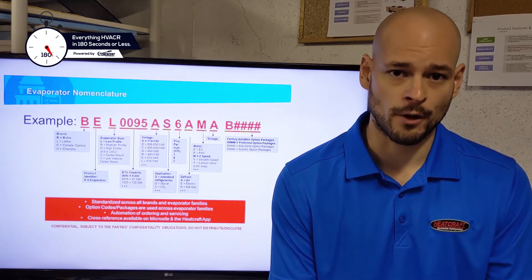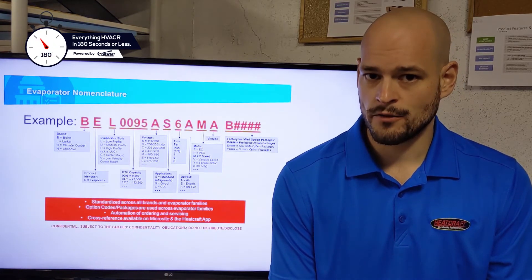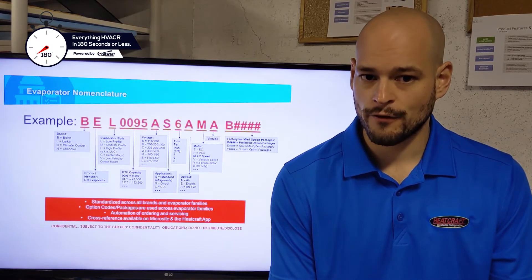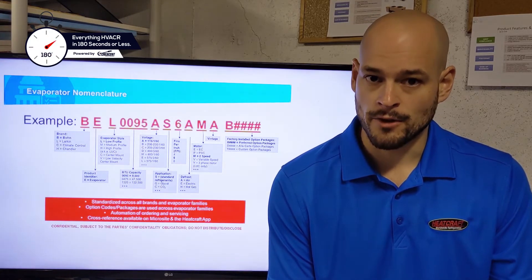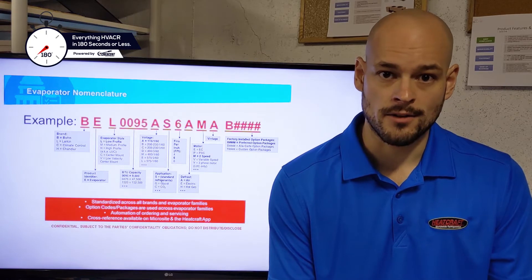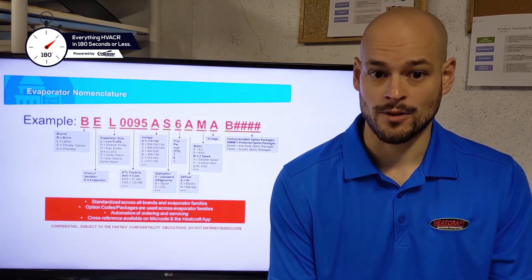Your next digit is going to be your voltage code. This has not changed from our old nomenclature. A is 115 single phase. B is going to be 208-230 single phase. C is going to be 208-230 three phase, and D is going to be 460 three phase.